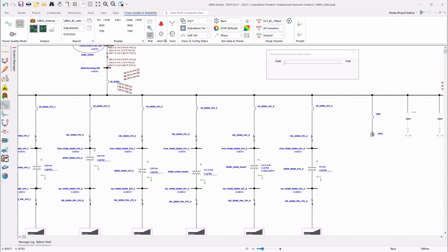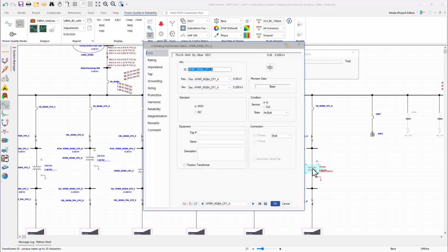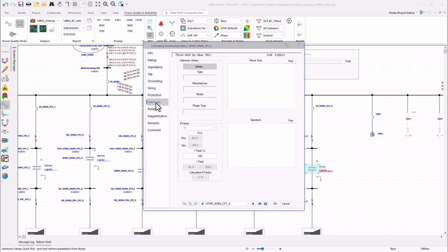So measurement of harmonic currents in the network and determining the heating effect of these non-sinusoidal currents on the transformers is an important step in determining appropriate transformer size and K rating. So K factor of the load harmonic currents is calculated in ETAP to determine the required K rating of the transformers feeding the nonlinear loads.